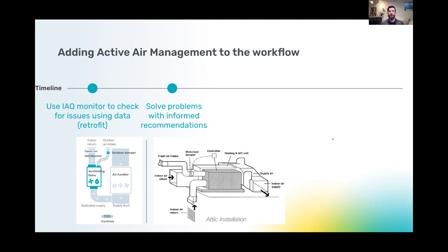Particularly, these will be light commercial projects, kind of out of our normal ballpark of residential. We'll get into some, for example, food processing facility where they want to see what is the effectiveness of our system. And actually what I meant was, do you try to monitor the supply side, after the filter as well, just to get the two data points at the same time? Yeah, we do see that sometimes when there's a building owner, they care more about what is the air I'm supplying to the tenant. Whereas in single family, when the owner is the tenant, they just want a system that controls, and being in the return, we see what's coming back, we can control appropriately, and then it's cyclical. So whatever's happening in supply eventually circulates back to the return.